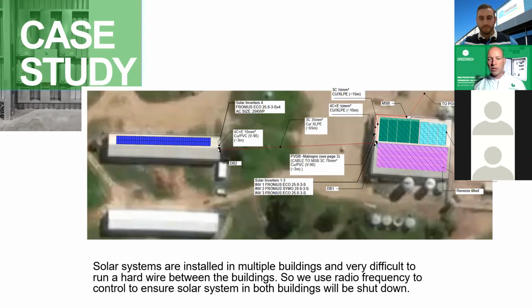What we're then using is some radio units and contactors that are linked together. In case the grid protection tells the inverters to drop out, that's a standard radio signal, and it then activates the contactor remotely to shut down the solar inverter. That way you can save yourself a lot of digging or running a cable, which adds a lot of cost. It's a cheaper way around it and helps you out.